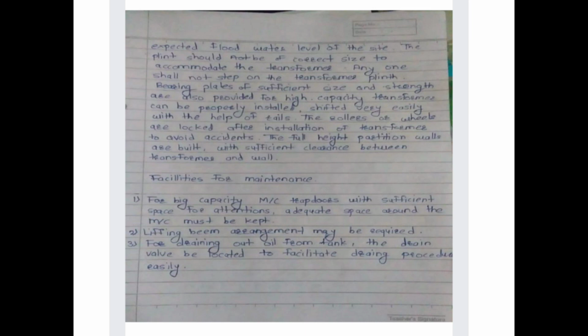First of all, the facilities for maintenance. First, for big capacity transformers, trap doors with sufficient space for attention. Adequate space around the transformer must be kept. And second, a lifting beam arrangement may be required. Third, for draining out oil from the tank, the drain valve should be located to facilitate the draining procedure easily.